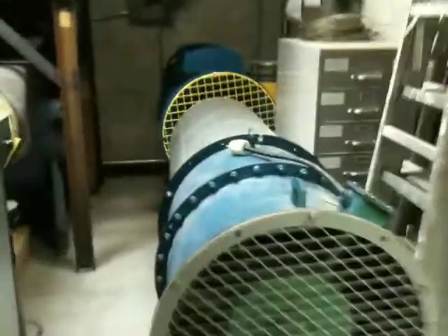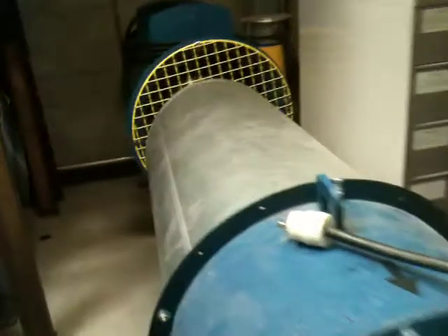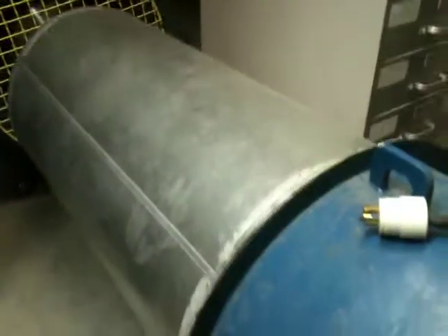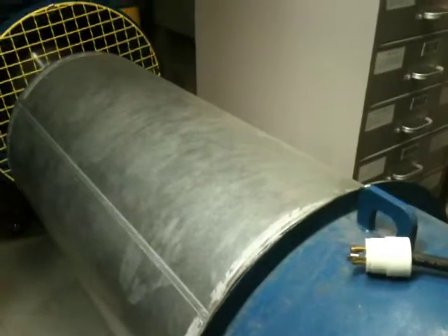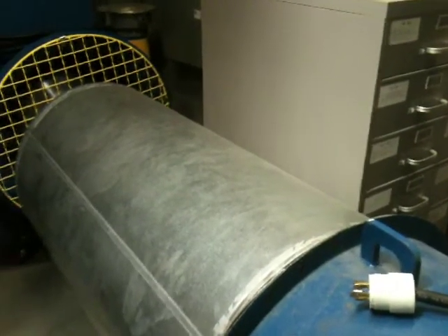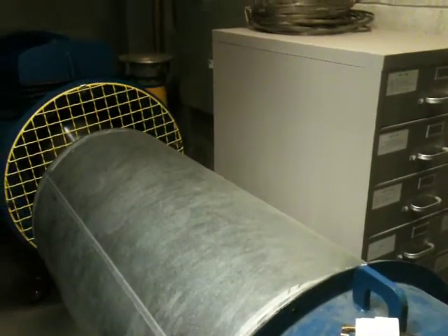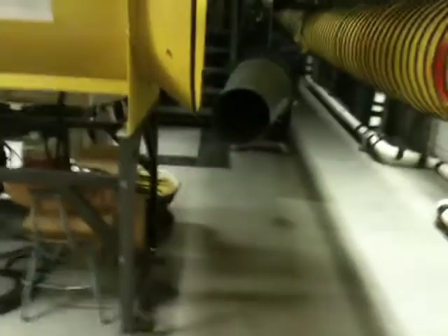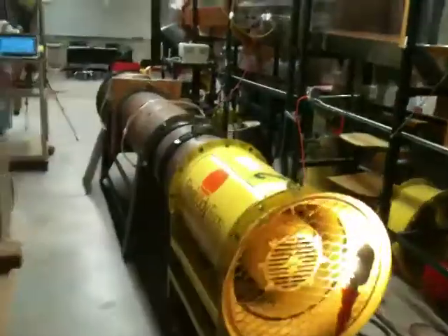Finally, around here is our second 5 horsepower fan, and you can see that this one has a long cylindrical duct attached to it, and the duct is actually attached to this fan's inlet. So we will connect this duct to the discharge from the first 5 horsepower fan, the one that we just saw, which will itself remain connected to the test stand, and we'll have the case of 2 fans running in series.